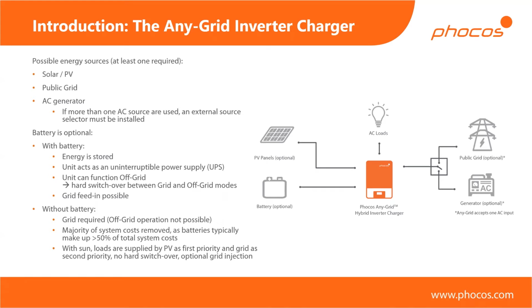And for this to work well, obviously with your existing loads, we need to have this very quick switch over time, so that you don't have any of your loads which would temporarily turn off during the switch over time. So that just doesn't happen. We haven't met any loads so far that will not handle that 10 millisecond switch over time. For those interested, that's 1/2 sine wave. A question right now is how the MPPT is handled without a battery. I'll get into more detail on that later.